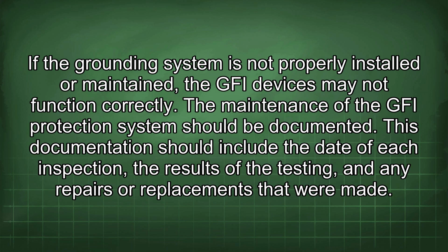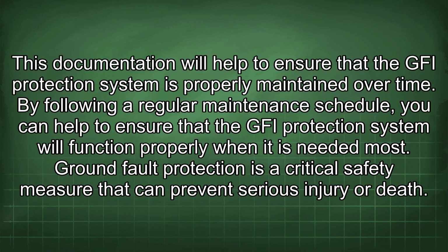This documentation should include the date of each inspection, the results of the testing, and any repairs or replacements that were made. This documentation will help to ensure that the GFI protection system is properly maintained over time. By following a regular maintenance schedule, you can help to ensure that the GFI protection system will function properly when it is needed most. Ground fault protection is a critical safety measure that can prevent serious injury or death.